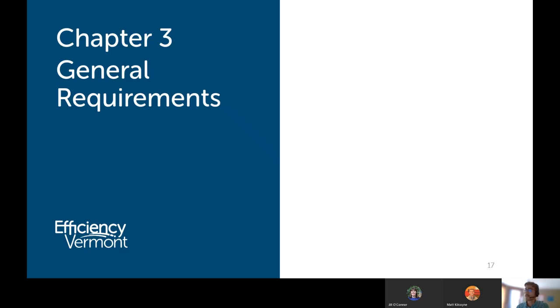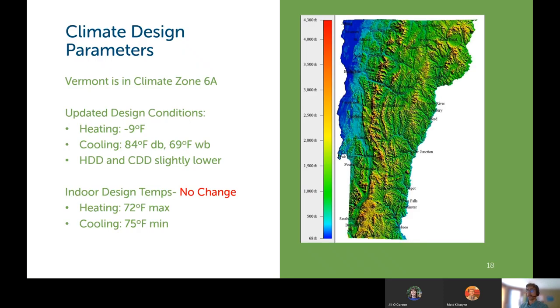Okay, chapter 3 are some general requirements of the code. And this is just one slide. What's in here is what the design climate parameters are for the state of Vermont. So when designing mechanical systems and envelope systems for Vermont, all of Vermont is within climate zone 6A. There are some updated design conditions in this version of the code. The heating temperature has increased slightly from minus 11 Fahrenheit to minus 9. The cooling, I believe, is slightly updated, or it could be the same, where it's 84 degree dry bulb and 69 degree wet bulb outdoors.